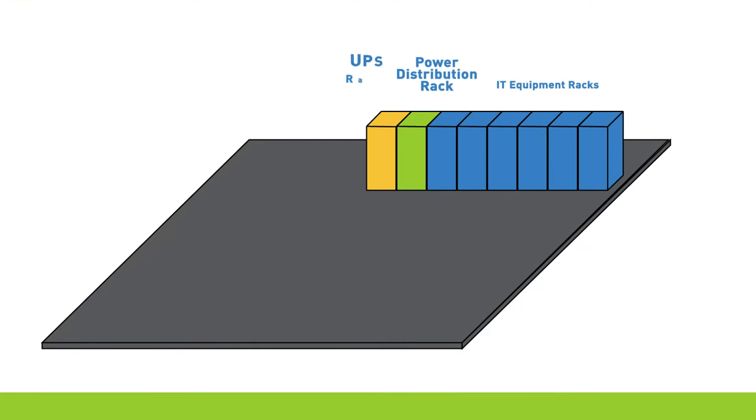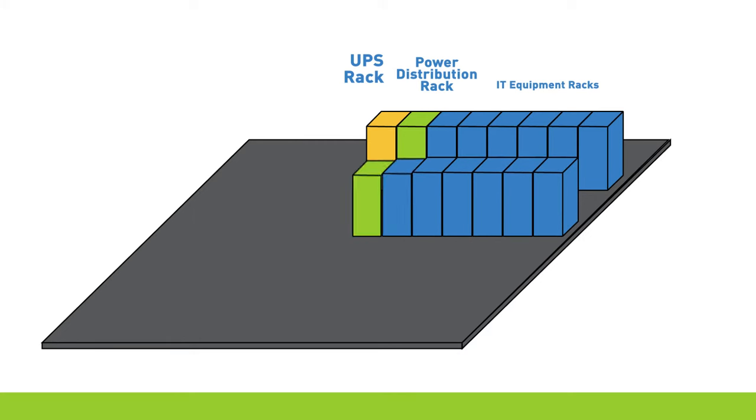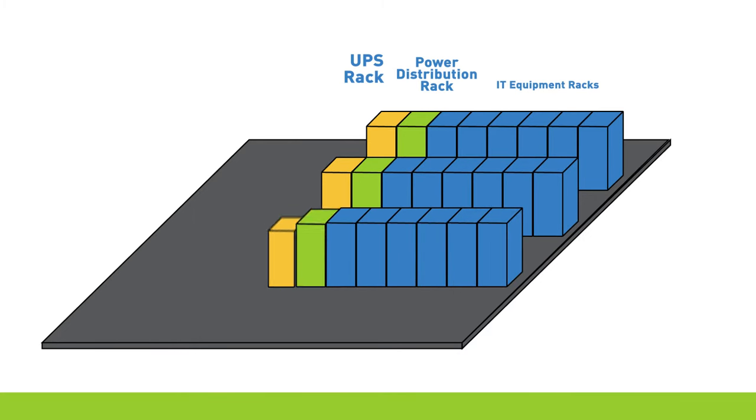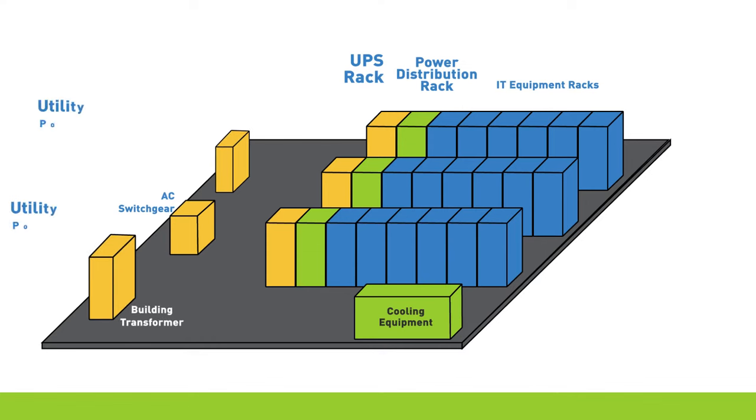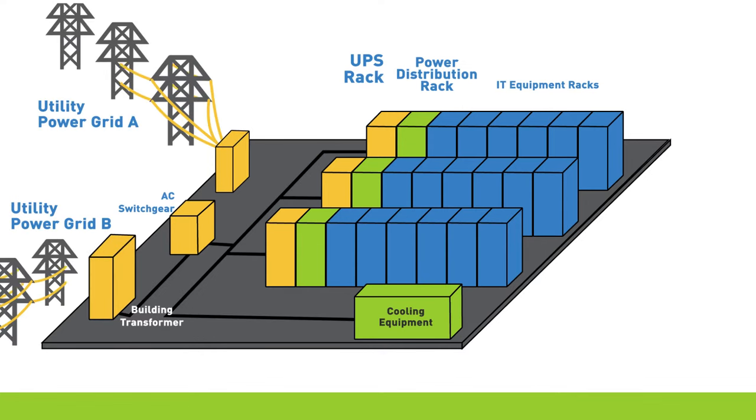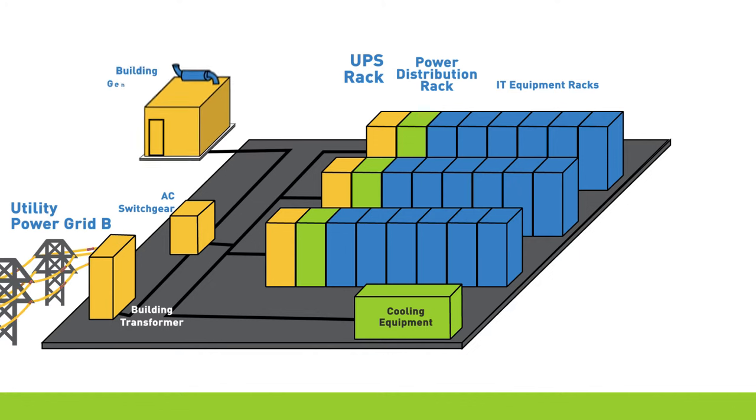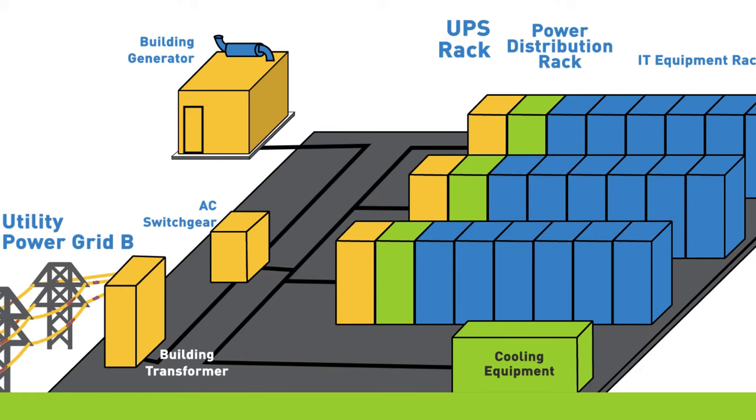The best goal for a Class 4 data center would be to have two feeds from separate utilities or from at least two main substations. This would provide two completely redundant power chains including redundant access to the utility power grid. Since this is very expensive and usually not feasible, the most popular option is to backup the utility power feed with diesel generators.